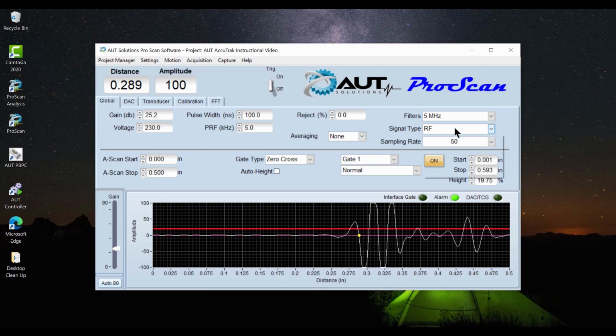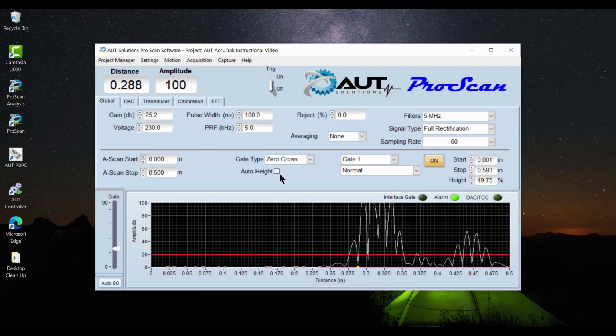We're going to change our signal back to fully rectified. We'll turn on auto height, which will allow the system to add gain to keep the signal in there up to 10 dB. So we have our auto height set. Our gate is going to be at 20% screen height. Our range, we are going to cover all the way down to a 1/2 inch. So we'll just adjust that. Change our start. Auto height, screen range looks good. Now you will notice that the gate is a little bit off the screen. We'll simply come in here and change that to 2.1.